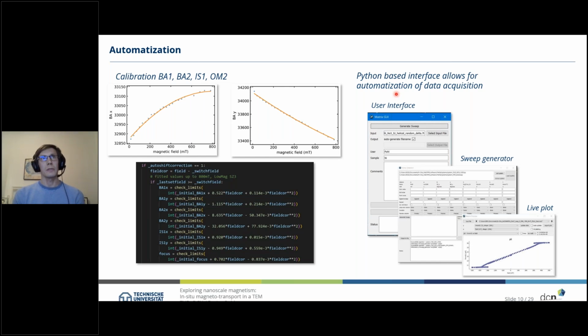Since we're changing the objective lens and therefore also beam deflections and shifts and so on, we needed to calibrate the beam shift, which in our microscope, a JEOL F200, is called BA1. The BA2 is the tilt of the beam. We have an image shift as well, and we have a slight defocus or focus of the focusing lens, the mini objective lens, and all of them are calibrated as a function of the magnetic field. This was done by hand, reshifting the beam, for example, recalibrating the microscope for different settings of the magnetic field value.